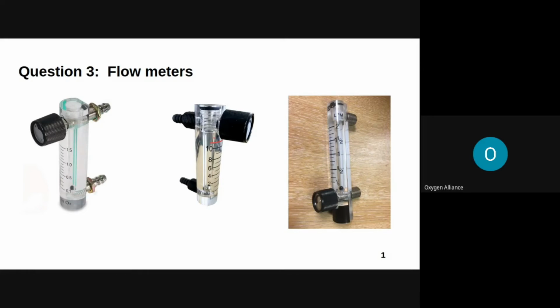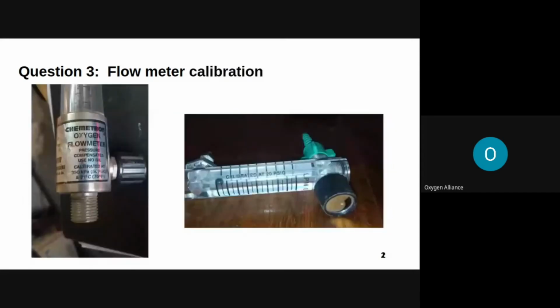Another thing to look into is the pressure at which the flow meter is calibrated. Otherwise, you can actually get false readings. Like most of the flow meters we see, some, like the one in the graphics on the right side, are calibrated at 20 psi. So if you are replacing the flow meter, the new one also has to be calibrated at 20 psi. And the one on the left is calibrated at about 50 psi, which is 350 kilopascal. So these are the things you need to look into when you want to change the flow meter.